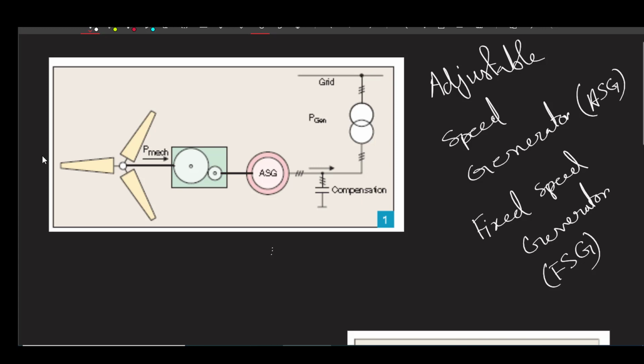Moreover, the adjustable speed generator can dynamically compensate for torque and power pulsation caused by the back pressure of the tower. This back pressure causes noticeable torque pulsation at a rate equal to turbine speed times the number of rotor wings.